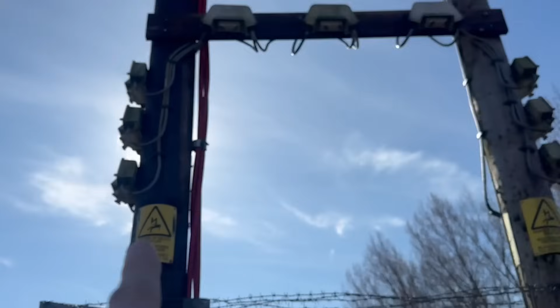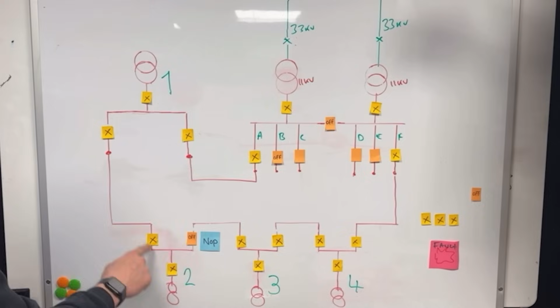I've labelled my substations 1, 2, 3, 4 and my breakers with letters. So what we're going to do now is we're going to have a fault. This is what the ring main enables you to do. At the minute, substation 1 and substation 2 are fed from A, and substation 3 and substation 4 are fed from F. Pause the video and look at that and prove to yourself, because here we've got a normally open point.